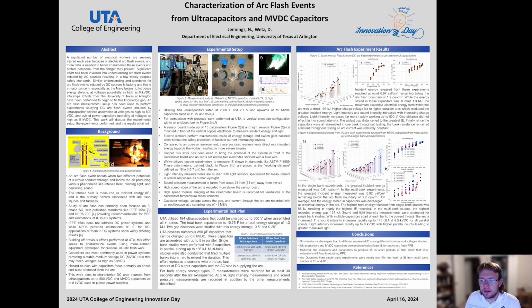And finally, since the capacitor banks were studied throughout all the testing, the bank resistance, which is kind of an important thing for many modeling circumstances, remained constant throughout the testing. And so what this would imply is that the current throughout all of the arcs would be roughly the same, because the current and voltage just depend on the arc itself and not really the system that is behind it, because the system is the constant here. Moving on to figure 4, which demonstrates our multi-bank and single-bank experiments.